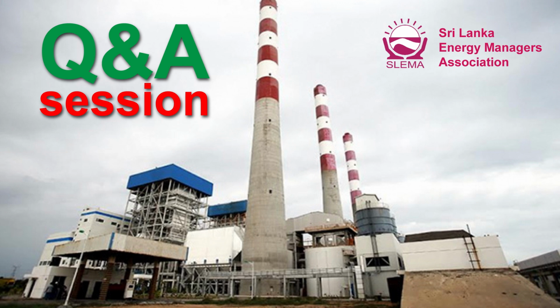As a mechanical engineer, my proposal to you, this may be very naive, is just to have a quick start diesel engine for the auxiliary power, then this would have been avoided. Am I right, or am I grievously mistaken? Yes. Not necessarily, but the problem is that when you stop any auxiliary equipment, as I have shown you in the middle slide, the priming of the pump, the lubrication oil, all those things will not be there. So to prime the pump, it takes some time. Now that's the problem even with the startup of the diesel generator.